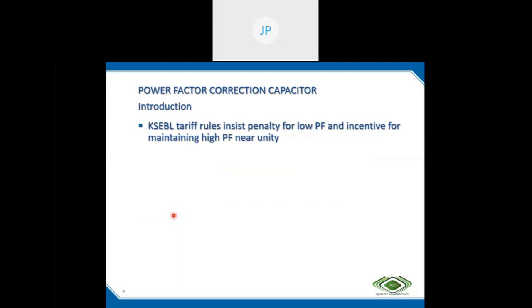And the penalty is to discourage maintaining low power factor. And they are promoting energy efficient use by providing incentive for maintaining high power factor. Nowadays, energy cost is increasing year by year or once in 2 years. So saving has to be taken care of by the consumers and the utilities. It is generally achieved by mitigating low power factor and thereby power factor penalties.